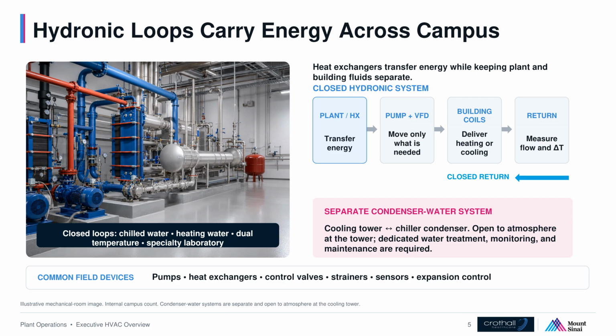Hydronic systems are the campus bloodstream. Closed chilled water, heating water, dual temperature, and specialty laboratory loops circulate the same treated fluid. Heat exchangers pass energy between plant and building systems while keeping the fluids separate. Pumps with variable frequency drives should move only the flow the system needs. Coils deliver the heating or cooling, and the return temperature difference tells us whether that energy was actually used. Valves, strainers, sensors, expansion control, and water quality all matter. Condenser water is different. It is open to the atmosphere at the cooling tower, so it needs dedicated treatment, monitoring, cleaning, and maintenance. A pump command alone proves nothing. Verify flow, pressure, temperature difference, valve position, and the condition at the coil.